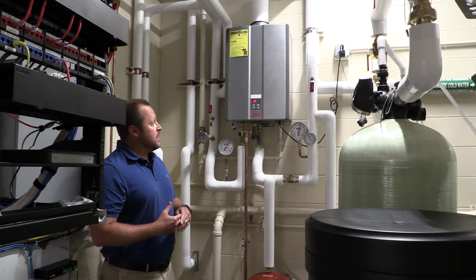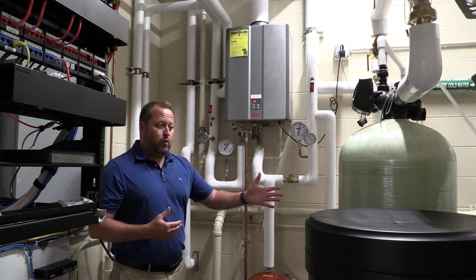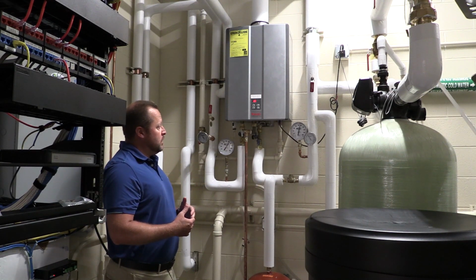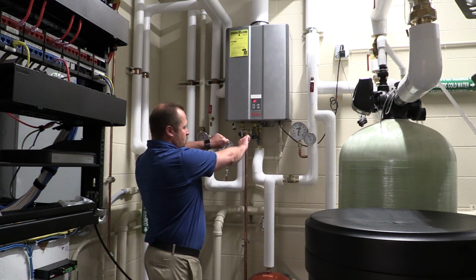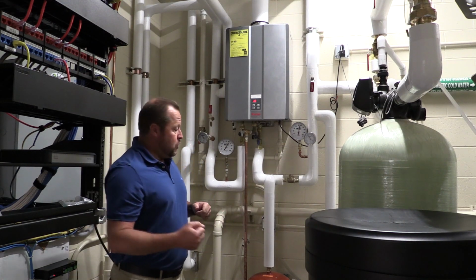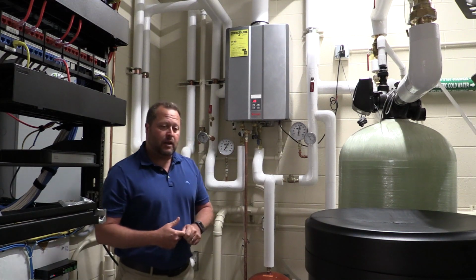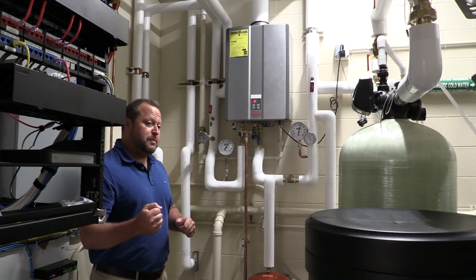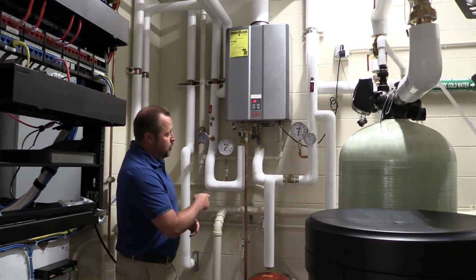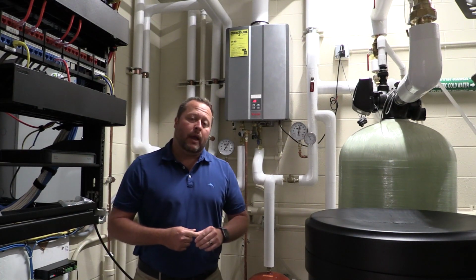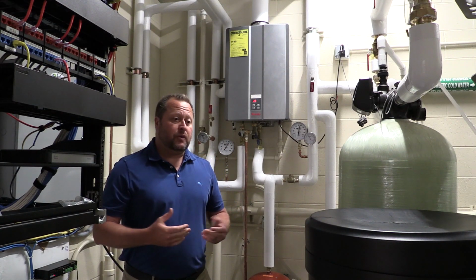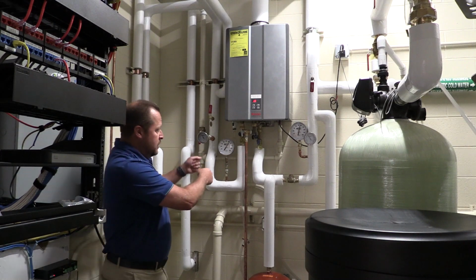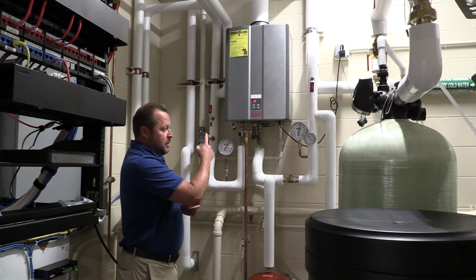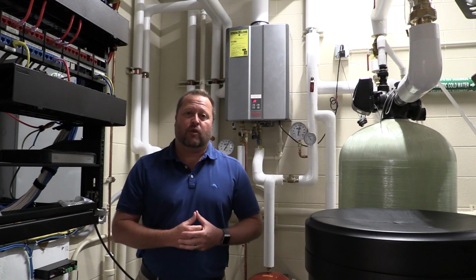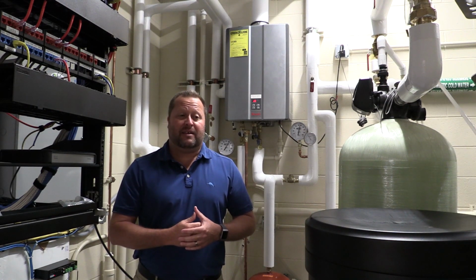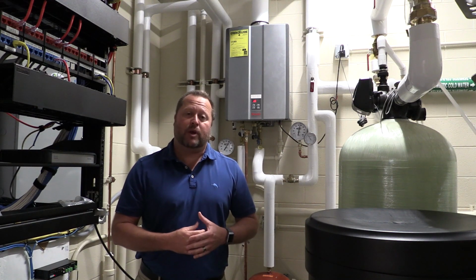To clean this unit, there is a stainless steel heat exchanger on the inside. They recommend, if it's softened water like you see here, once a year. And what you do is you basically isolate the heat exchanger by closing the valves here that supply the water to the unit. You hook up your hoses, you put a 5-gallon bucket down, fill it with 4.5 gallons of distilled white vinegar. And then you have a pump. They actually make a kit like this you can buy at distribution. You turn on that pump, you run the distilled white vinegar through that heat exchanger for roughly an hour. And that cleans all the scale and buildup from that unit and cleans it out. When you're done, you just basically pull the lines off, you close back down the valves, you open up the water, the domestic water, back to the unit, you're back in business. And we want white distilled vinegar because it is a food grade product that it's in your water supply. It's not going to be harmful if you ingest a little bit of it.